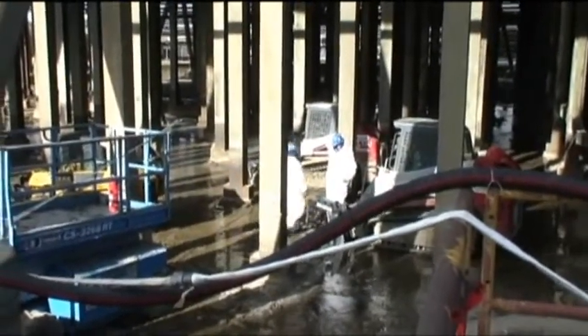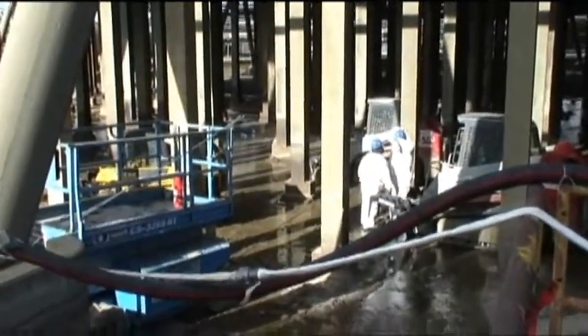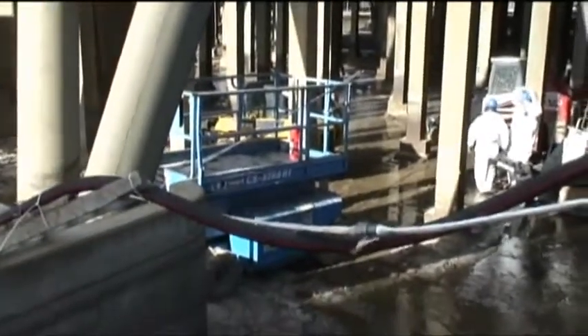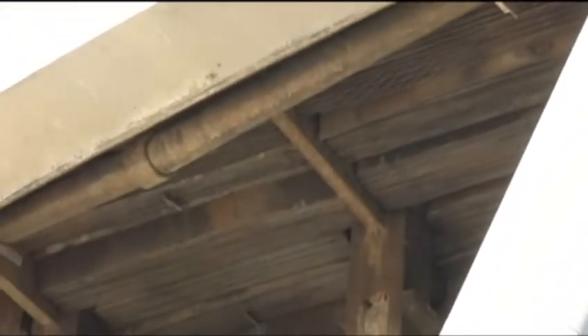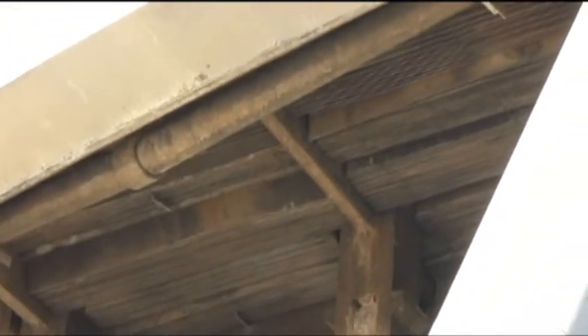And so our operators here are waiting to get back in and hit the pile. Use the scissor lifts in the basin to get up to access underneath. And you can see what it looks like underneath. You can see where it's missing a lot of the material that hangs in those little ledges, and all that material is falling out. That's why all this is getting replaced. The pipe you see up there is the de-icing header, which gets removed. They don't really work very well, is what I've been told. They will not be reinstalled.